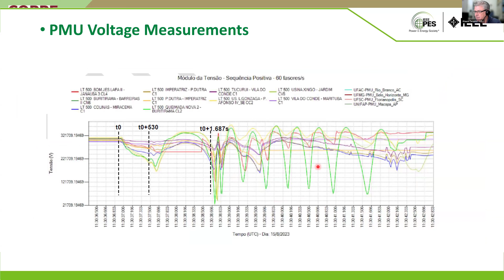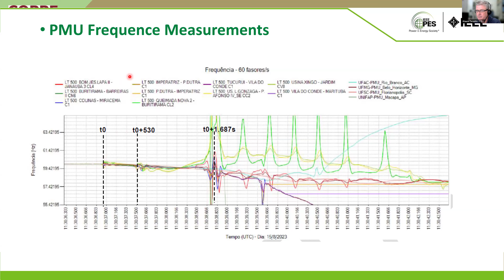Then this is also a larger window of those voltages. You can see here the out of step, the swings of voltage, and here the frequency of the system. The frequency was not a big problem. You see here, after half a second, so it was not a frequency problem. It was a reactive power problem.